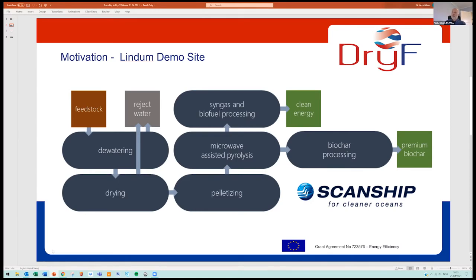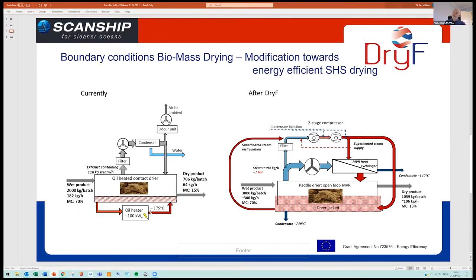So how did we do this? Our traditional dryers for cruise ships handling sewage sludge and food waste in particular were paddle batch dryers, paddle type, with a heating jacket. And on ships, we use excess steam. In land-based aquaculture systems, we use electrical oil heaters to take very wet sludge into the machine for a batch, circulate air, condense the water, and also have some control of odors. Typically, we use 800 kilowatt hours worth of energy to evaporate a ton of water in these systems.